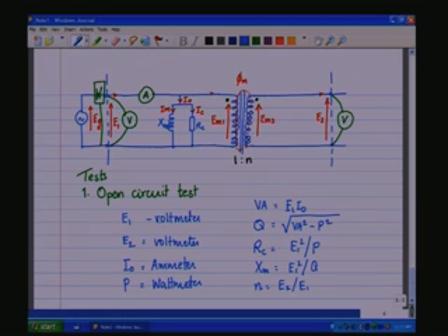So, based on these measurements, these parameters are obtained. Around 5 readings can be taken for these measurements, and an average of that found out, and that could be used for making the calculation here to improve the accuracy of the measurements. So, now we have obtained the core loss component, the XM, which is the magnetizing component, and the turns ratio from the open circuit test.